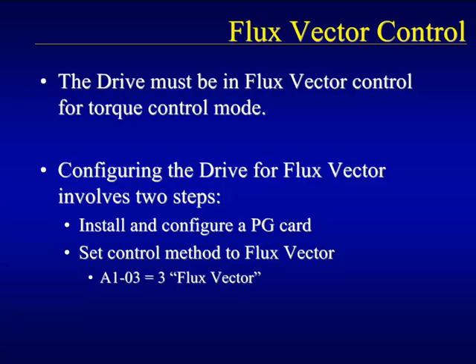In order to use Torque Control, the drive must be in Flux Vector Control mode. Configuring the drive to be in Flux Vector Control mode involves two steps. First, a PG Feedback Card must be installed and configured in the drive. And then the drive must be programmed to operate in Flux Vector Control mode by setting the control mode parameter A103 to Flex Vector.